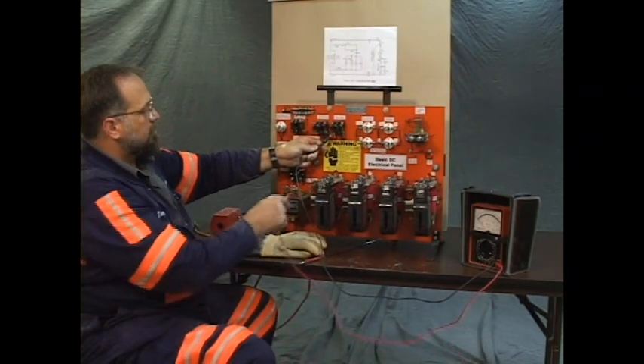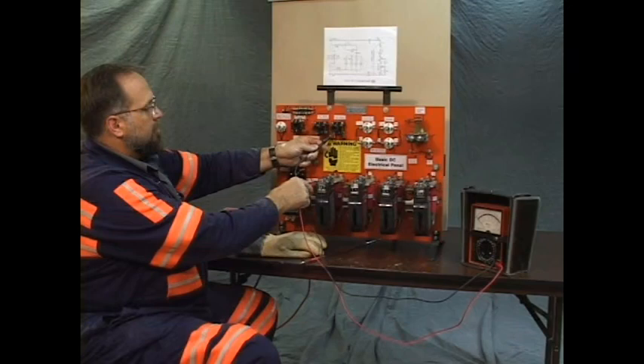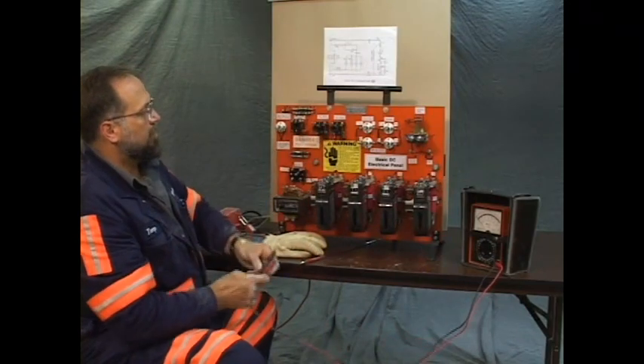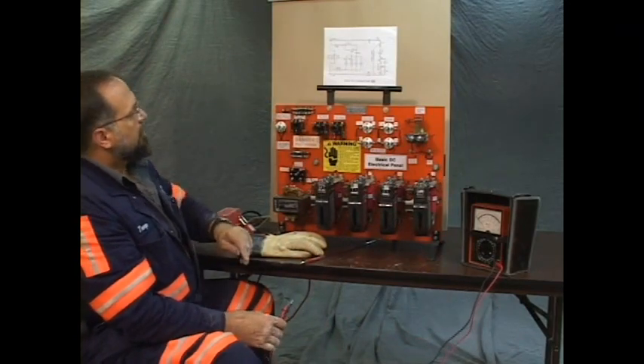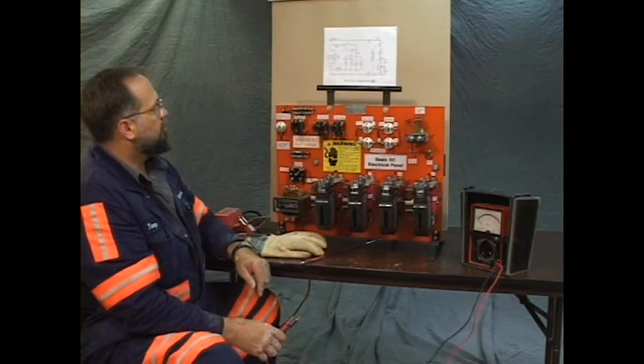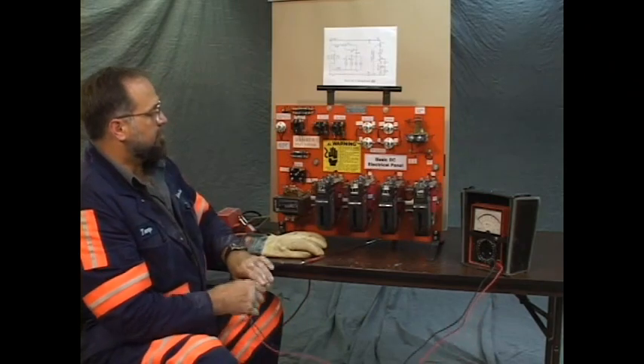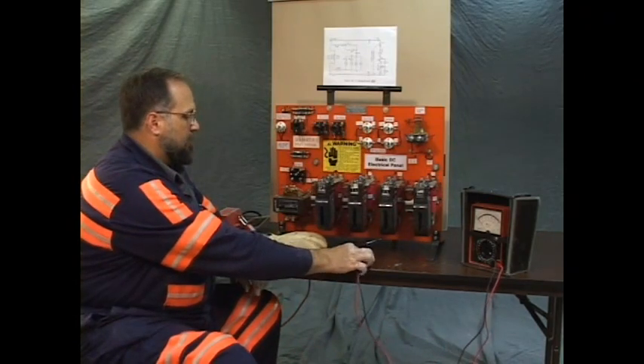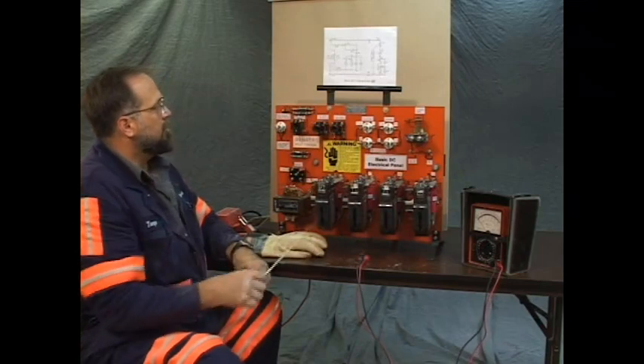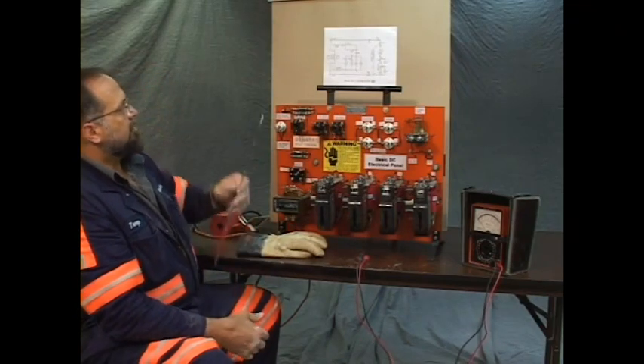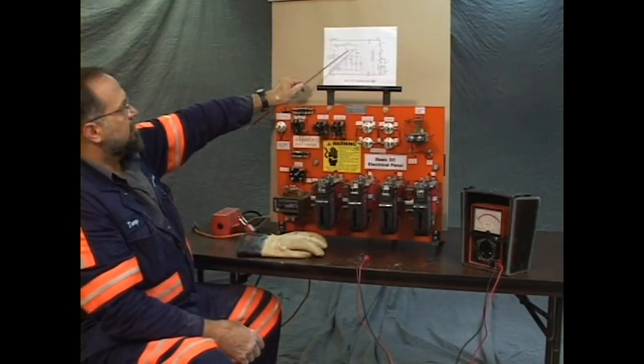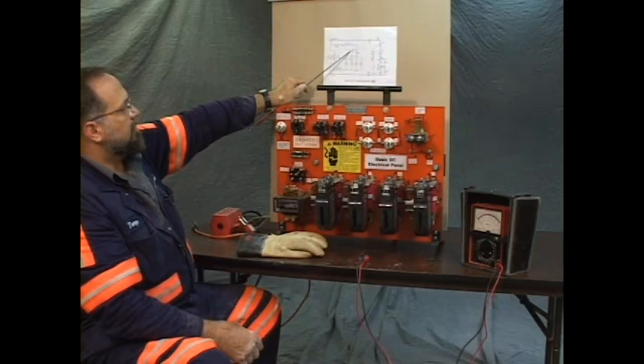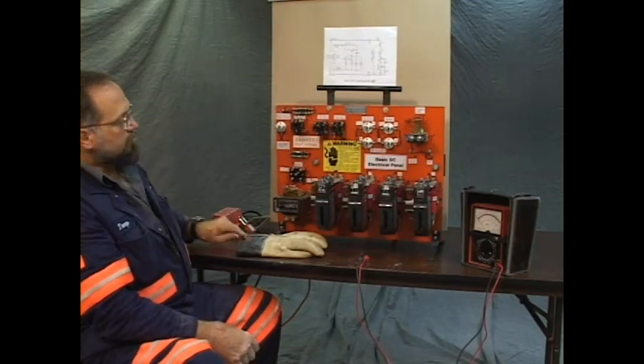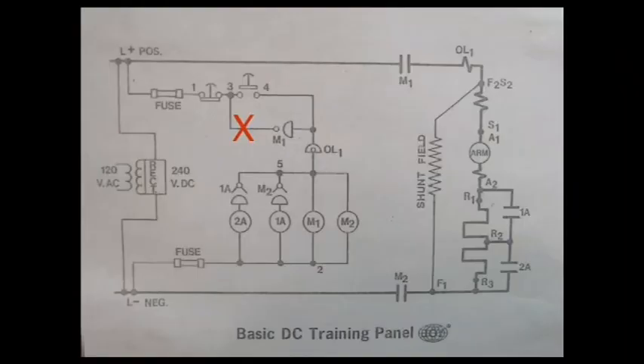Line side of the start switch to the line side of the mercury tube. The wire connecting these components is open. So the apprentice could list this problem as an open wire from the line side of the start switch to the line side of the M1 mercury tube. He could mark it on his print for testing with an X right there.